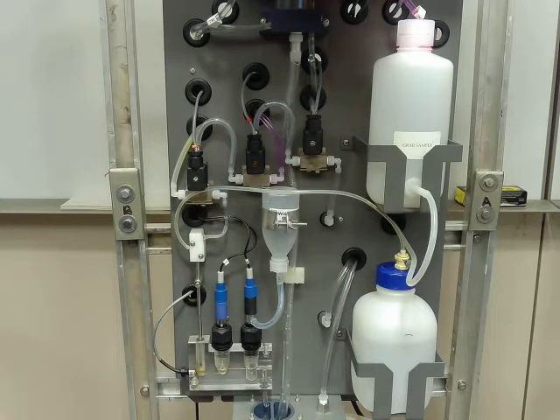And again, it should last you about 3 months, quarterly replacements, but if it's been more than 6 months, you would definitely want to replace it, regardless of how full that bottle is. And again, you would want to flush out that electrode, probably with some DI water, to make sure that solution can flow freely. So those are your big startup things which you have to do, especially if the analyzer is starting up for the first time. And obviously the replacements of those chemicals as you go through operation.